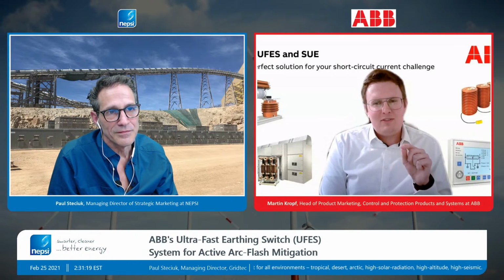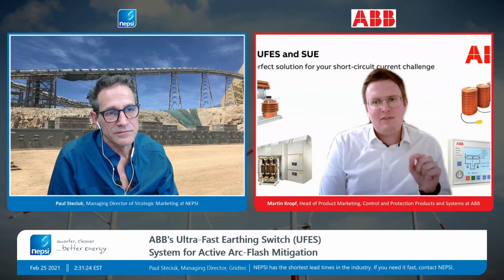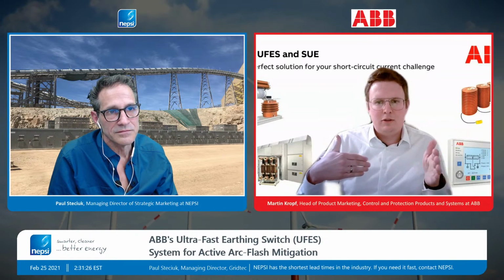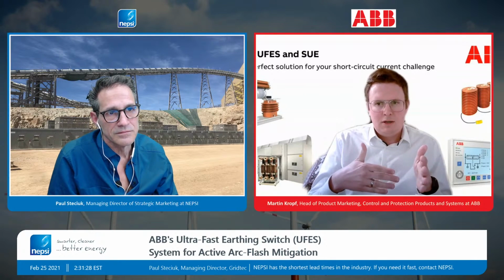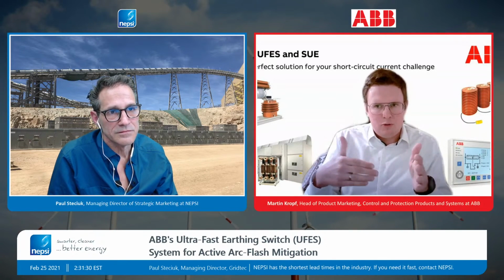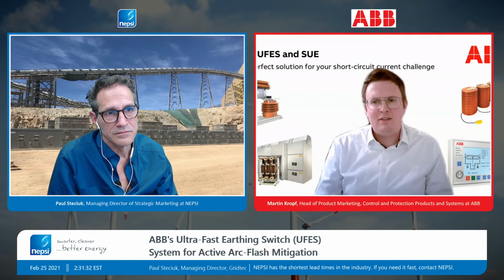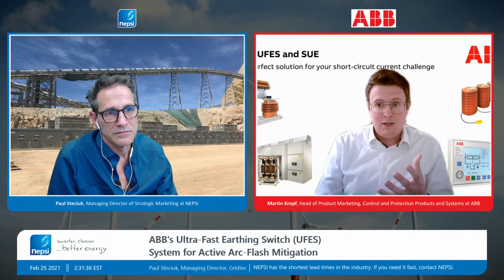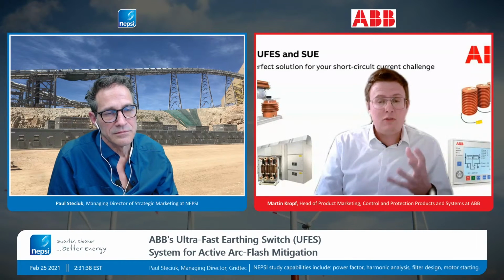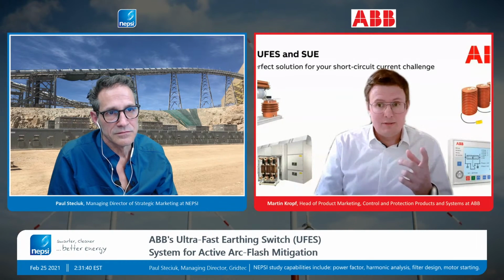What we have seen before was a passive internal arc test. In the passive internal arc test, the doors are all closed, everything is in closed mode. The key point is that the ultra-fast earthing system is always on - it's also on when the door is open.